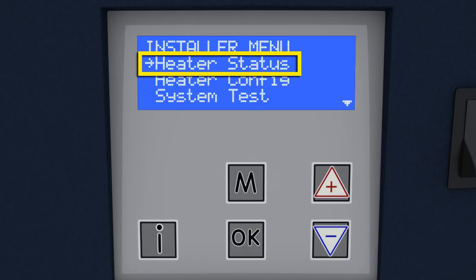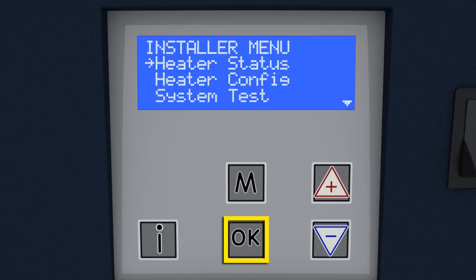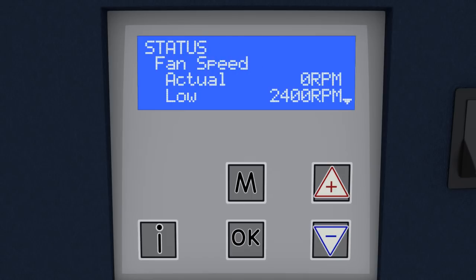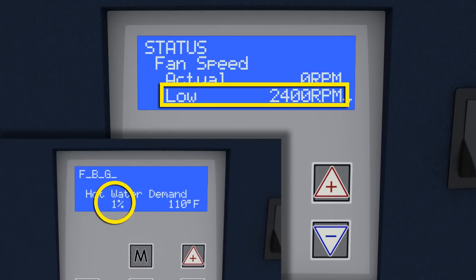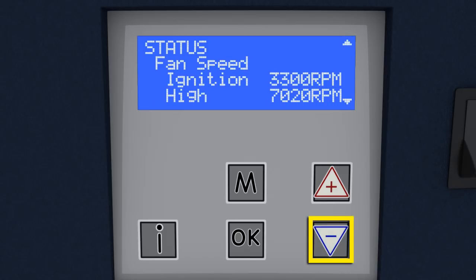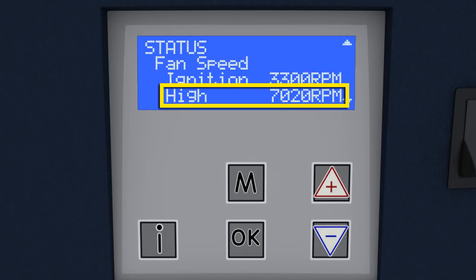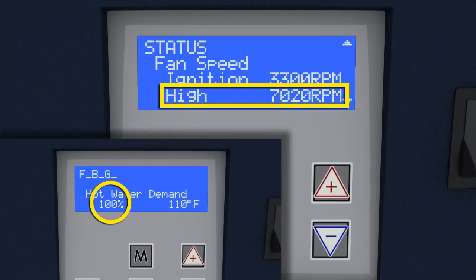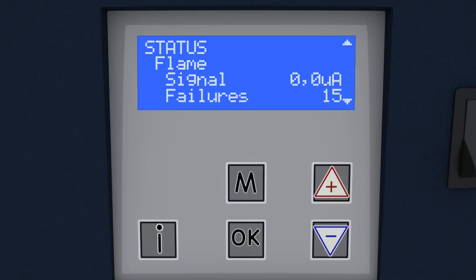To access the heater status submenu, select Heater Status and press OK. The first screen in the status menu displays actual fan speed and the low input fan speed in RPM. When the home screen shows 1%, the actual RPM will match the low input RPM. Use the down arrow to display the ignition speed and high speed in RPM. When the home screen shows 100%, the actual RPM will match the high input RPM. Use the down arrow to display the flame menu. When a flame is present, the flame signal will vary based on fan speed, but it will usually range between 5 and 7 microamps. The Failures submenu gives a running total of flame failures.